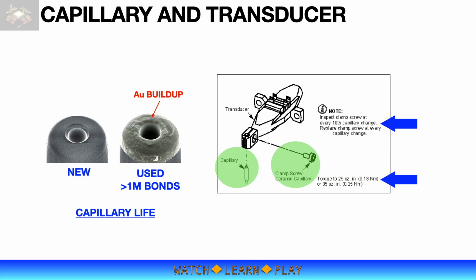Just to caution, clamp screw may look like just a regular screw, but its quality is critical. Do not use a cheap screw just to have a cost reduction project. Follow supplier recommendation if there's any, or buy from a reputable company that will provide you consistent material quality. Clamp screw must also be tightened at certain torque specified by supplier. Over or under tightening the screw will result in inconsistent performance of transducer and obviously inconsistent bonding results.